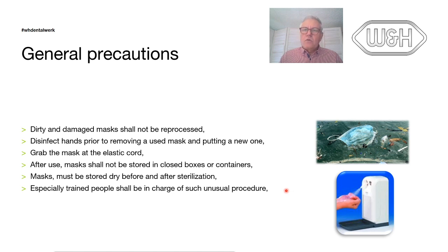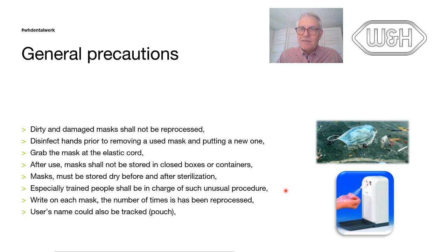You saw different loading methods of the autoclaves, so one person should be really in contact with the supplier and follow the instructions of the manufacturer, if there are some. Indispensable is to write on the mask, on the cord of course, how many times the mask has been reprocessed. And nice to do, I would like to put back my mask and not my neighbor's mask. So if feasible, put the name of the user, so the person can put back his own mask.